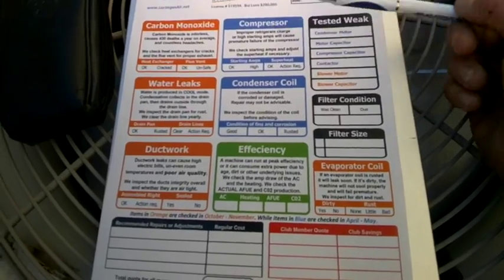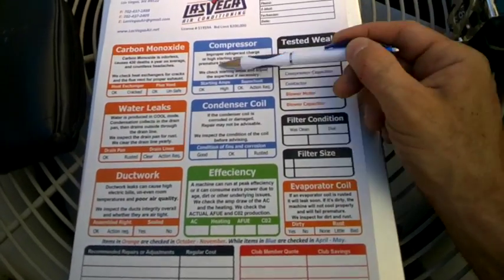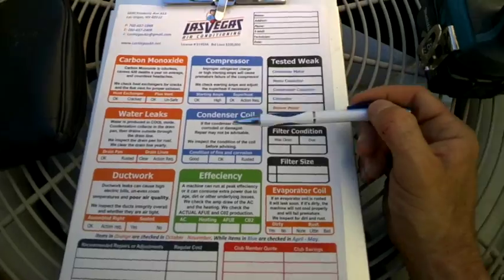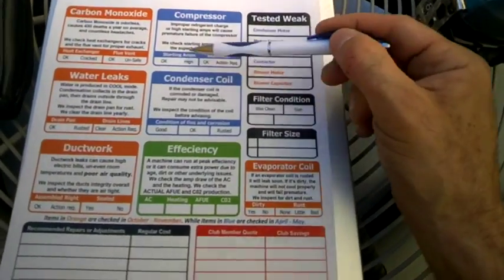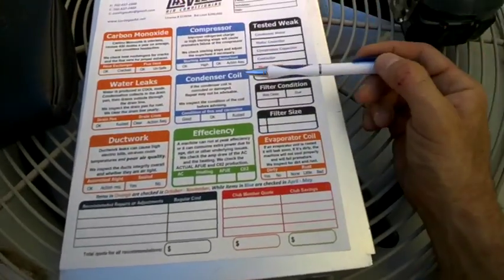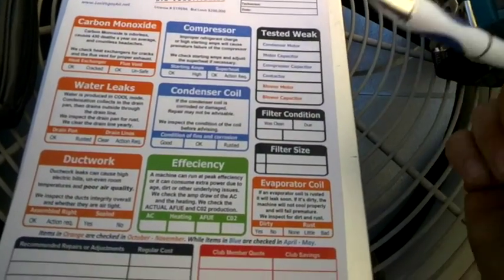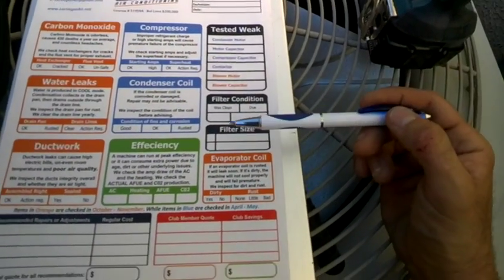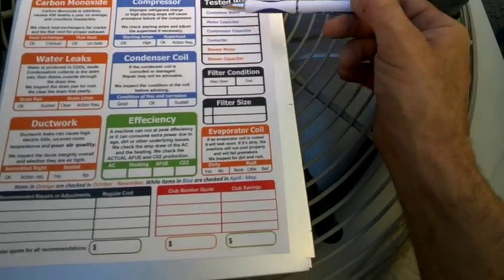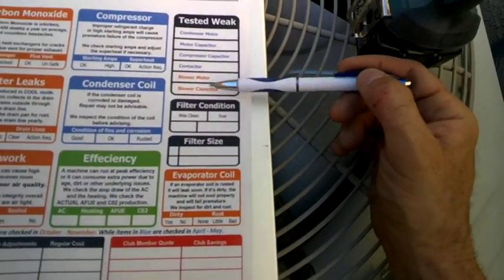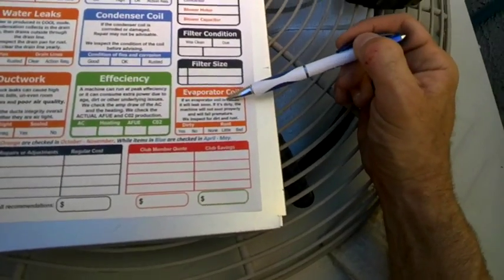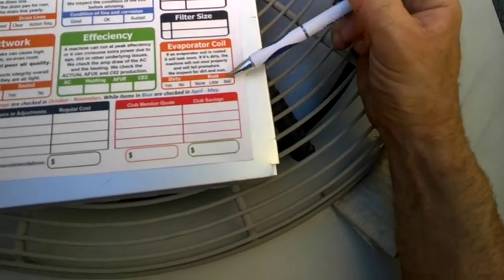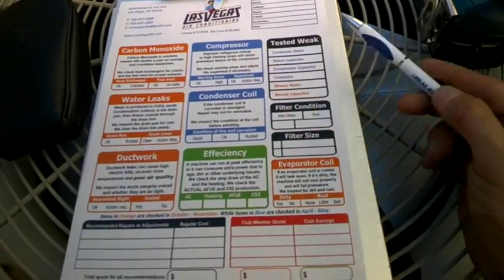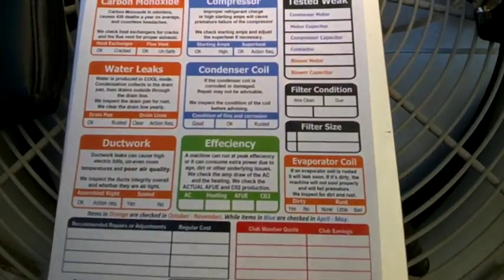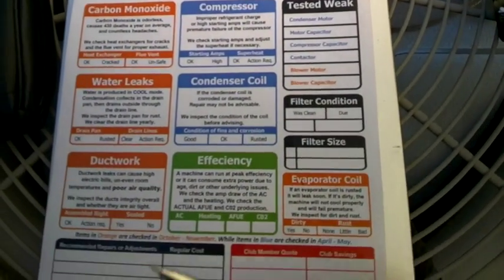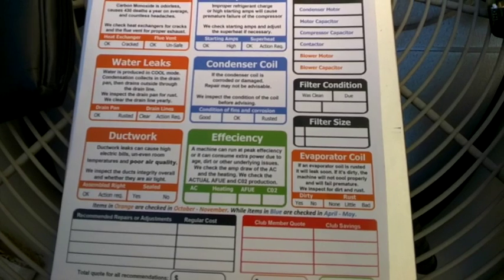And then the compressor is very important too, as it's the most expensive item and what people really want to last. So we check the starting amps, we check the insulation on the windings, superheat, the charge, and any item over here we check too. Condenser motor, capacitors, blower motors in the winter, the filters, the evaporator coil. Is it dirty or is it rusty? So that's kind of how this chart works and how it keeps us technicians focused on the right thing.